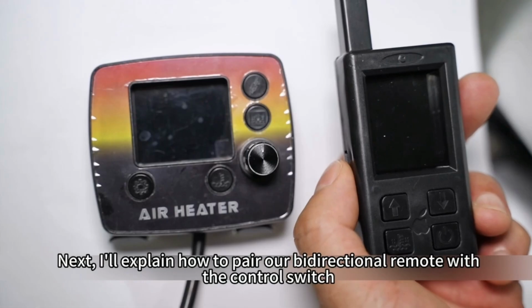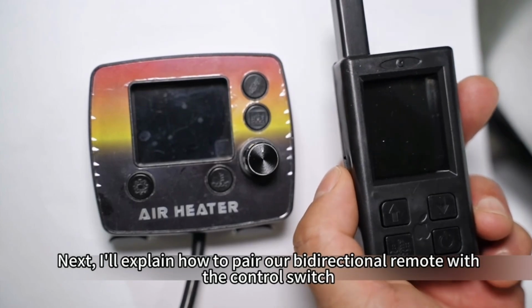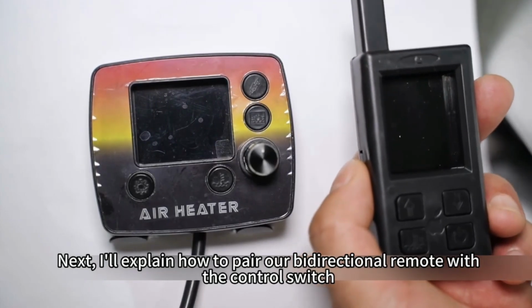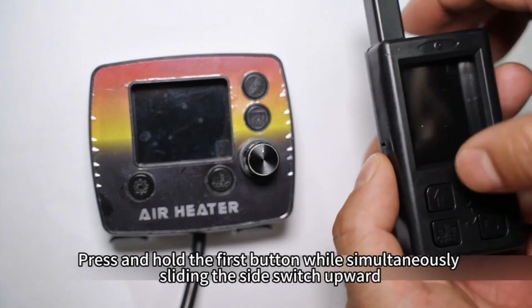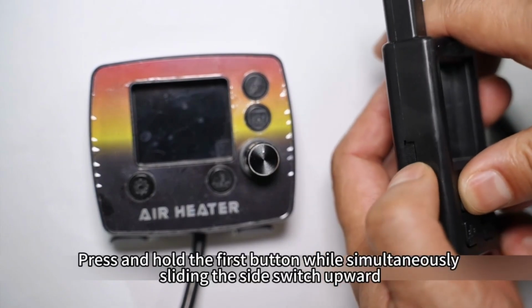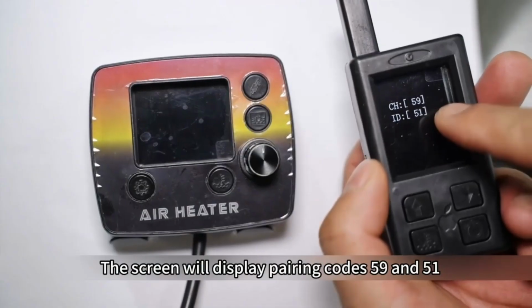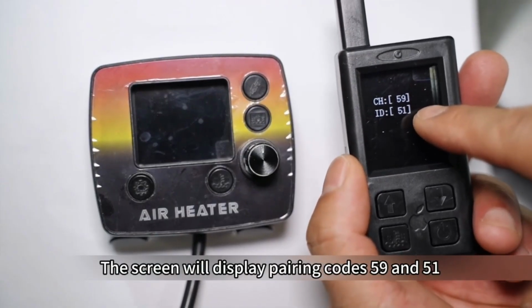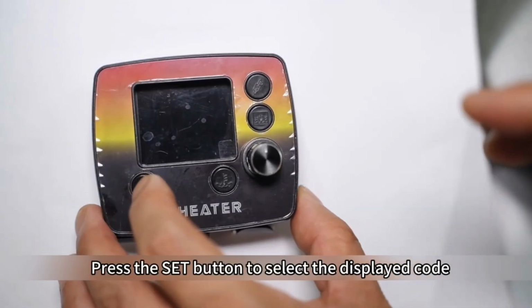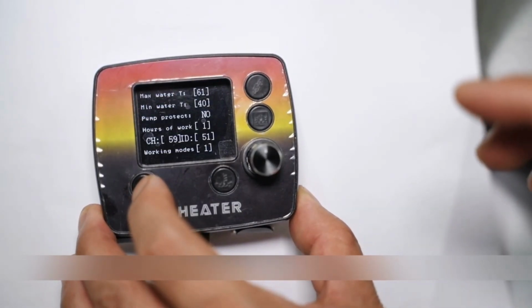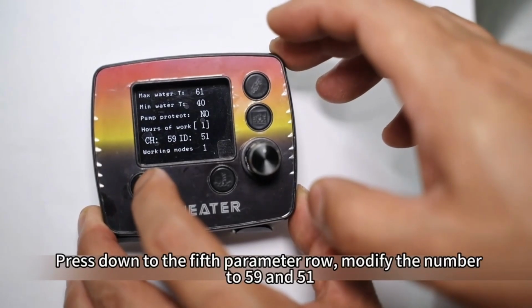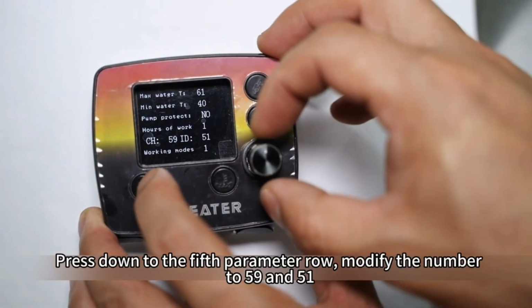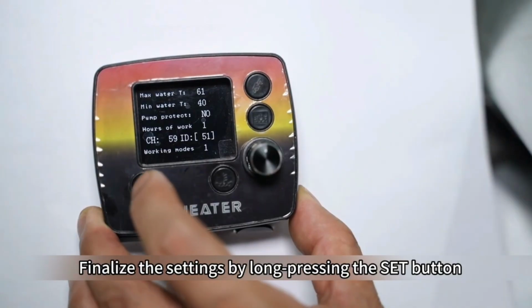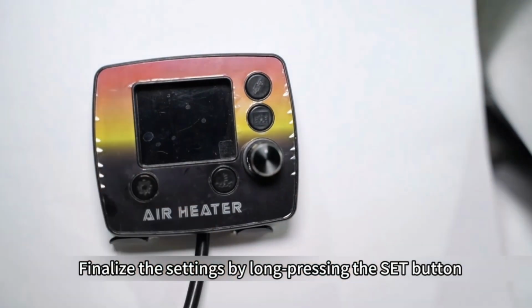Next, I'll explain how to pair our bidirectional remote with the control switch. Press and hold the first button while simultaneously sliding the side switch upward. The screen will display pairing codes 59 and 51. Press the Set button to select the displayed code. Press down to the 5th parameter row. Modify the number to 59 and 51. Finalize the settings by long pressing the Set button.